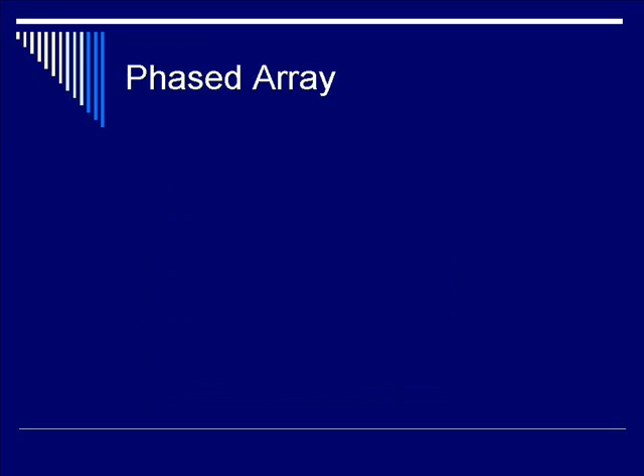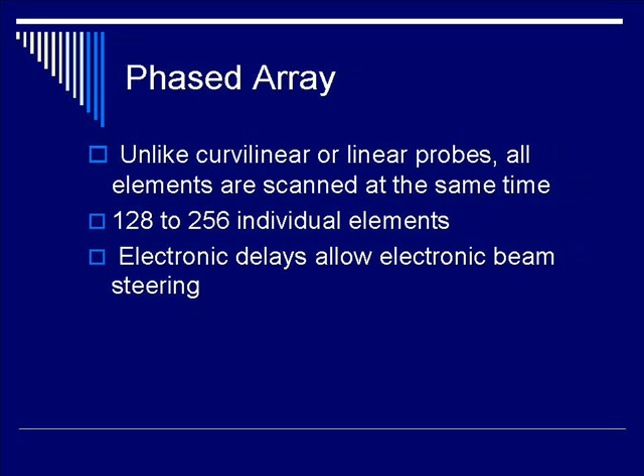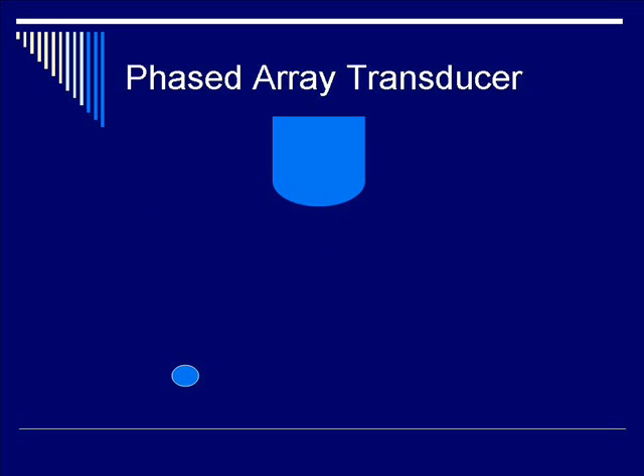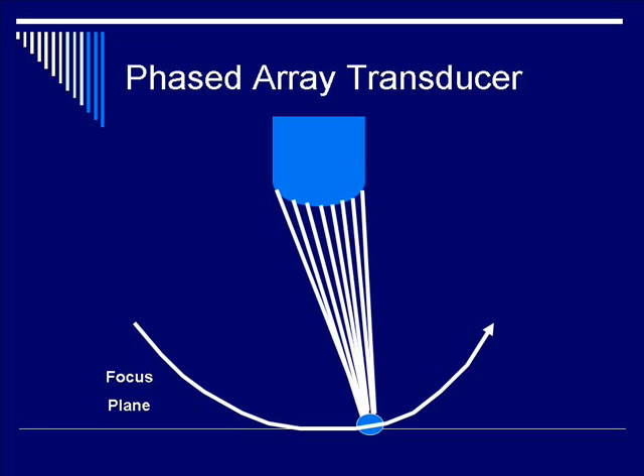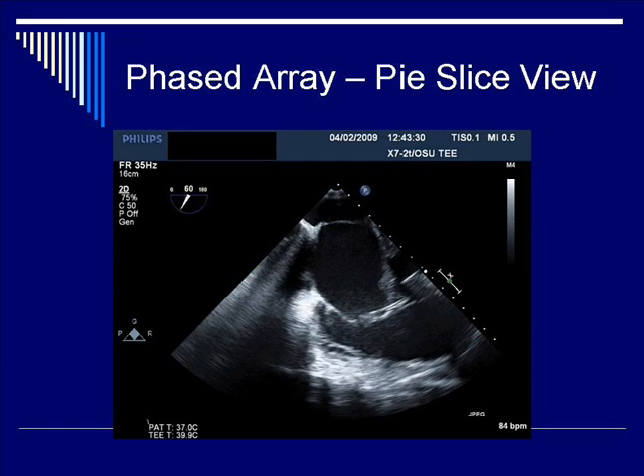Let's move on to the phased array. A phased array is different from linear or curvilinear arrays because all elements are scanned at the same time. It consists of 128 to 256 elements. Electronic delays allow the beam to be steered precisely. Beam focusing is done electronically, and it produces a pie slice scan pattern. Notice all elements are steered at the same time, focused going from left to right, steering at the same plane of interest. Clinically you can measure through a scan with the typical pie slice view.